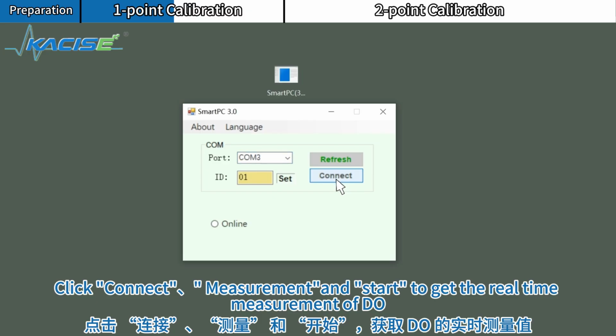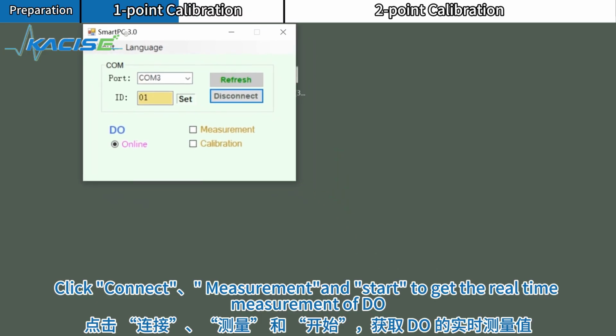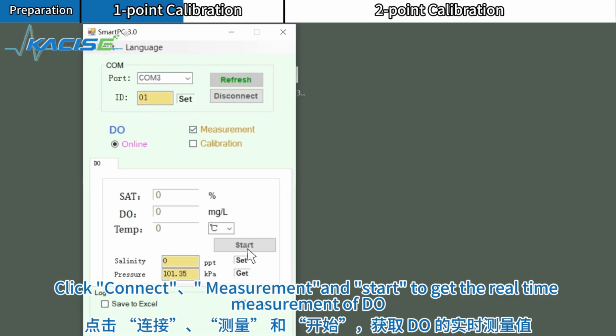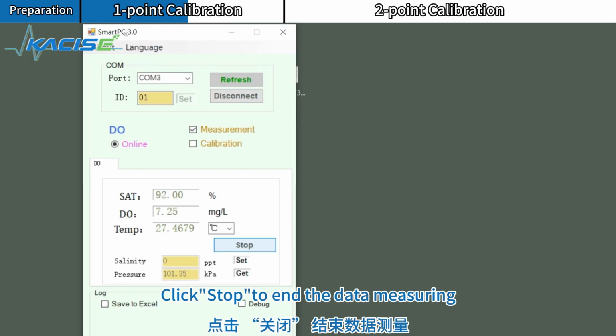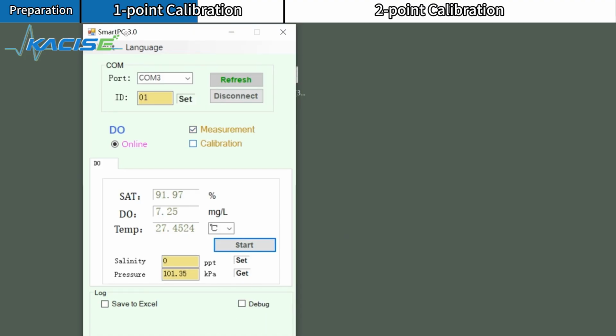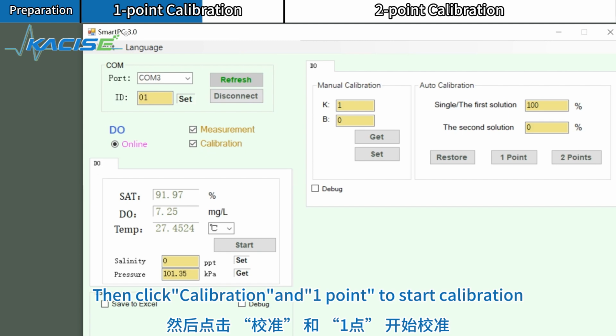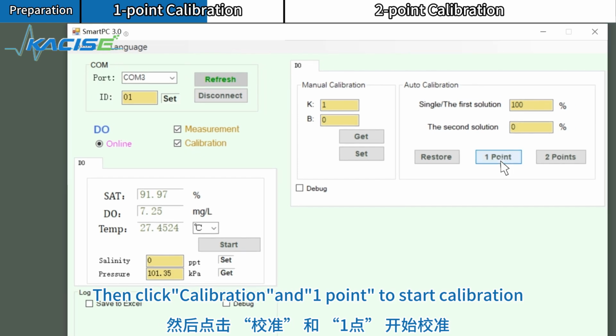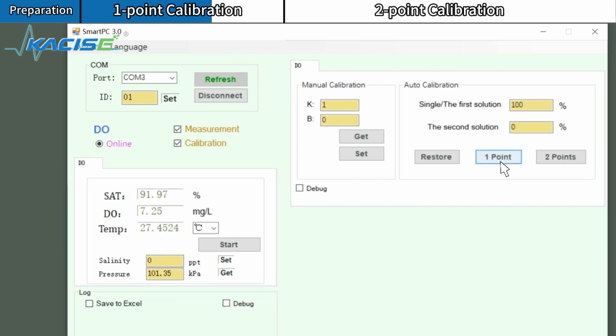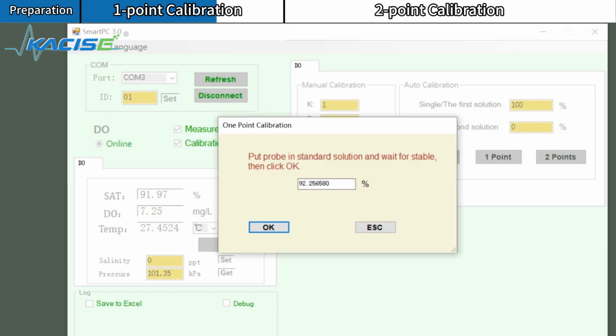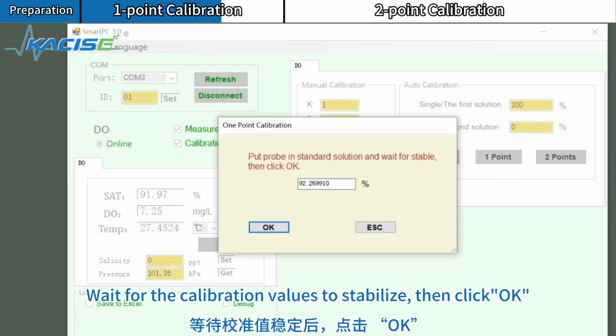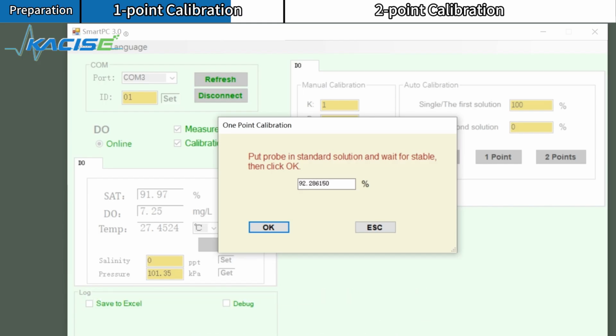Click Connect, Measurement, and Start to get the real-time measurement of DO. Click Stop to end the data measuring. Then click Calibration and 1 point to start calibration. Wait for the calibration values to stabilize, then click OK.